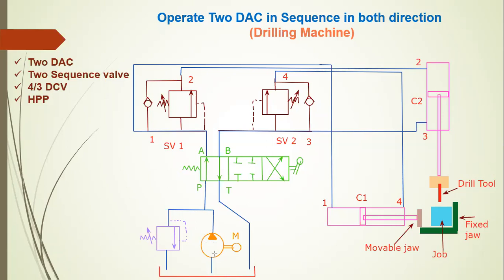Here this triangle says that in the hydraulic flow path, this point is called the inlet and this point is called the outlet. Here for the pressure relief valve, this point is called the inlet and this point is called the outlet. The hydraulic symbol itself also says what the flow path is. So never give an arrow direction in any hydraulic circuit.